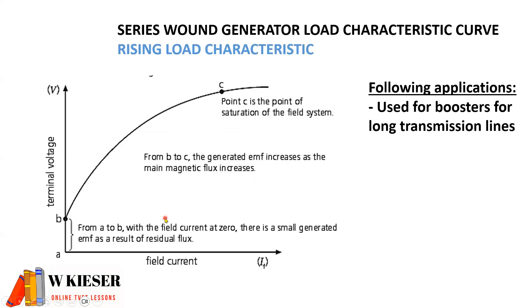The series-wound generator has a rising load characteristic curve. The reason for it starting at a certain point on the curve is because of residual magnetism. We have a steep curve but eventually it does start to drop off. Series-wound generators are used as boosters for long transmission lines.